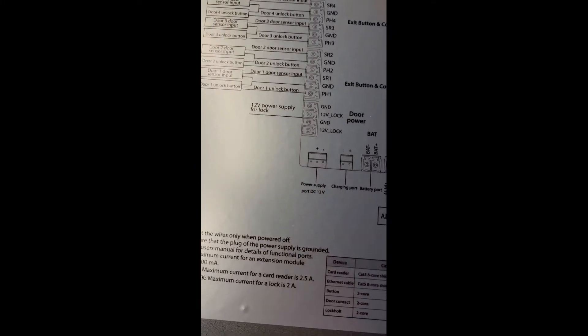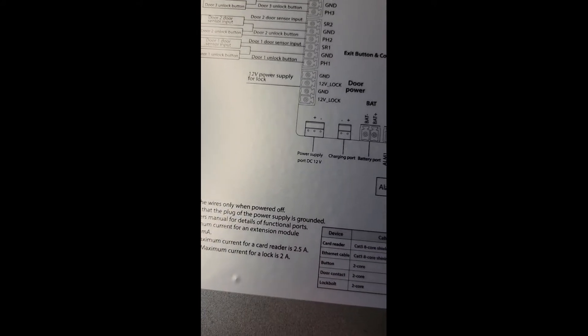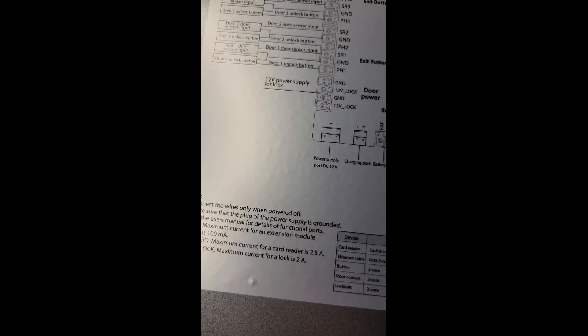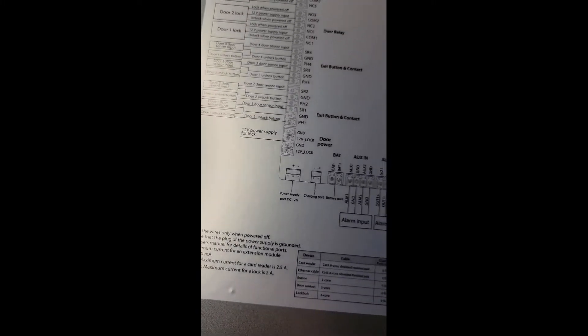For today's purpose, we're going to be utilizing the door lock one connection, the 12 volt power supply for lock connection that's rated for two amps. That's good for a couple door strikes or a mag lock. If you have more than one mag lock, I would suggest using an external power supply.